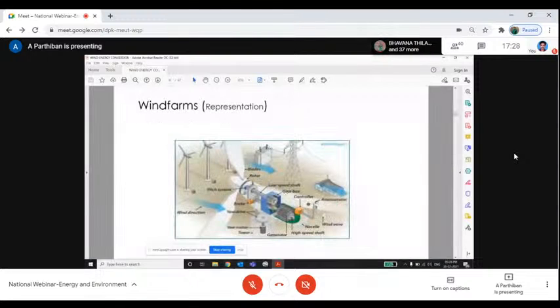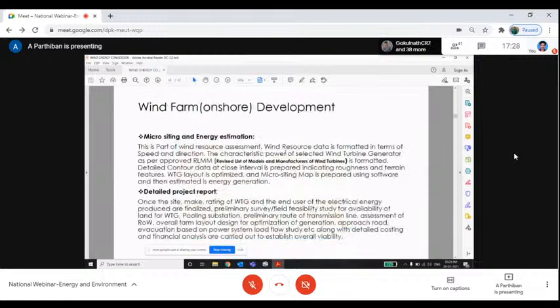So this is one of the typical wind farm structures. You can have some wind turbines which are connected via the grid network, and it goes to the pooling substation. From the pooling substation to the grid substation. From there it goes to the distribution network. So now we can enter into the core subject, how the wind farm is developed from the initial stage, and how it goes up to commissioning, and how operation and maintenance happens in wind farm developments.